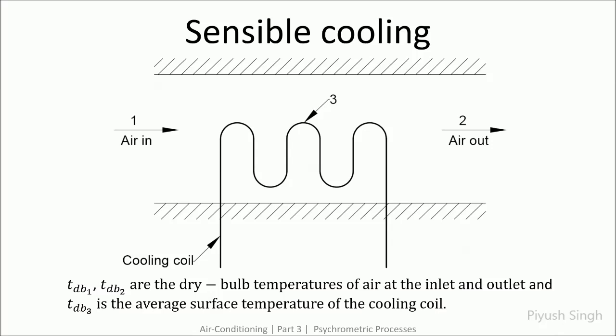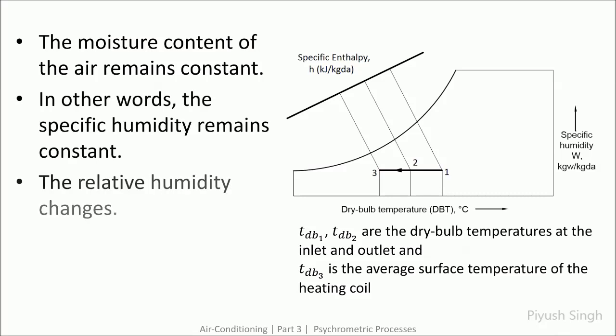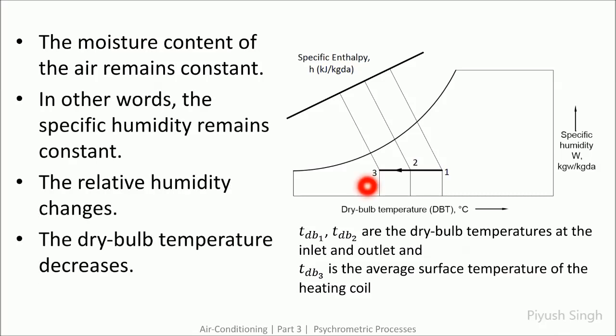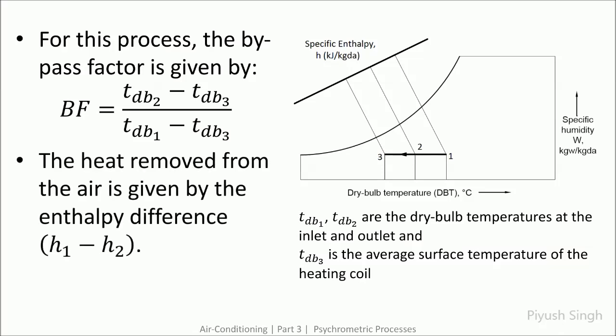Similar to sensible heating, we have the sensible cooling process, in which the coil temperature is lower than the dry bulb temperature of the incoming air but should be higher than the dew point temperature to avoid condensation. During sensible cooling, the total moisture content remains constant, so on the psychrometric chart it is represented as a horizontal line moving in the opposite direction. In this case, the relative humidity increases, the dry bulb temperature decreases, and there is a drop in specific enthalpy. Similar to the sensible heating process, this process also has a bypass factor.